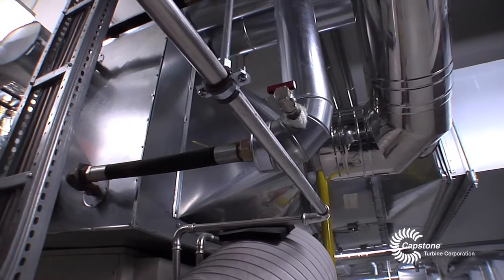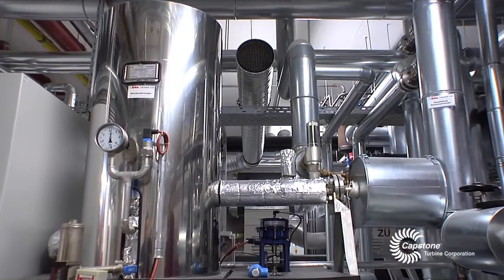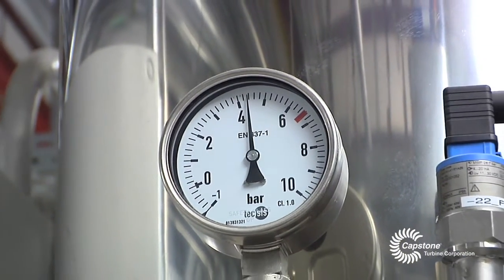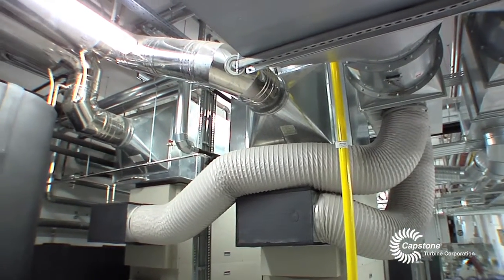The most interesting part of our system is certainly the heat exchanger. We installed an exchanger that is capable of producing heat in two stages: one is the production of hot water at 180 degrees carrying 15 bar of pressure, as well as regular water at 90 over 60 degrees. That really is a great way to use the entire exhaust air.